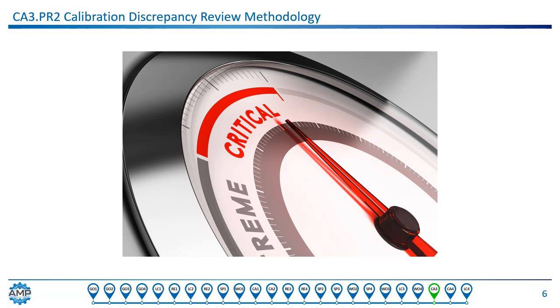Prioritization. It is important to understand if the out-of-tolerance finding could affect the quality, purity, or strength of the product. If a deviation is critical, it must trigger an investigation. It's a good practice to identify critical instrumentation and include that classification in the instrument asset record in the CMMS or in the calibration software. This can save some time that quality might otherwise spend collecting that information.